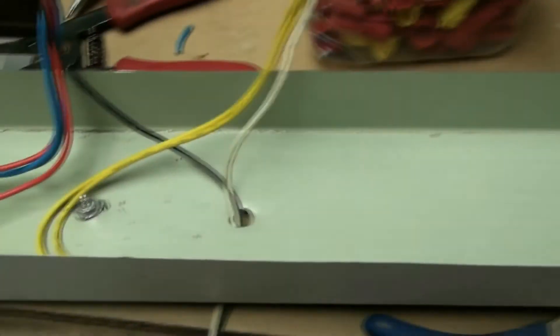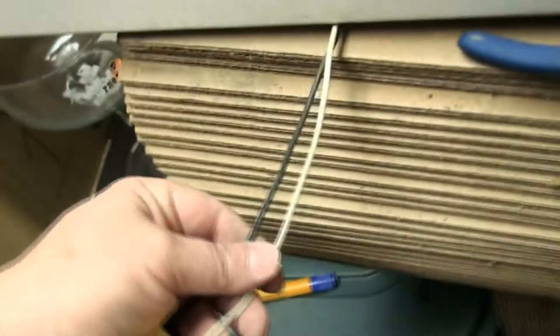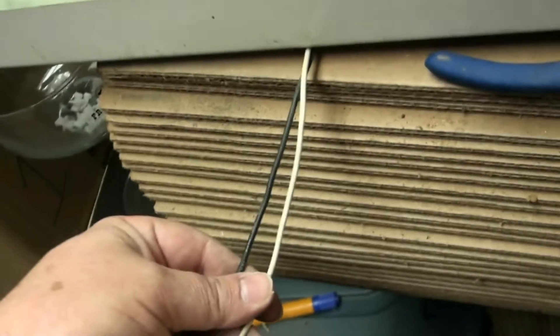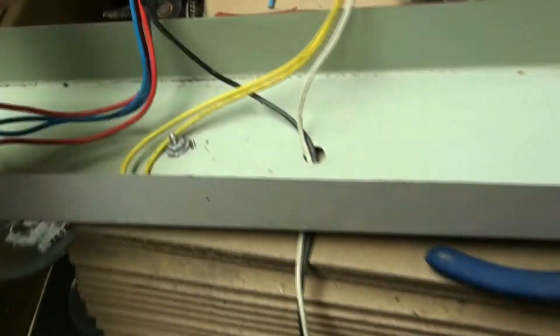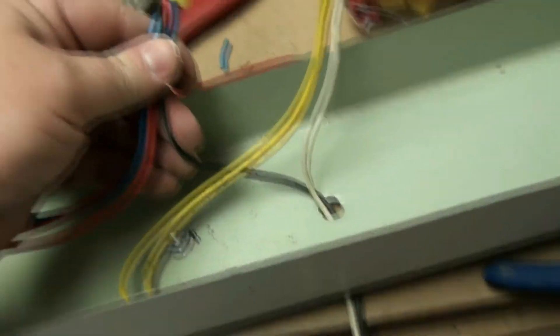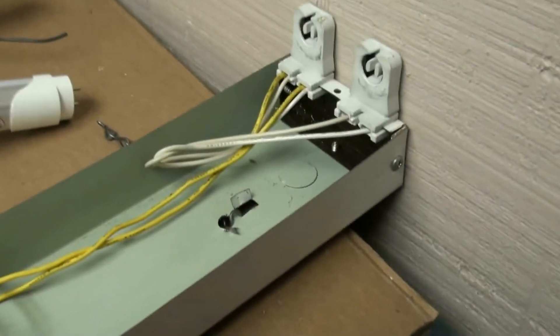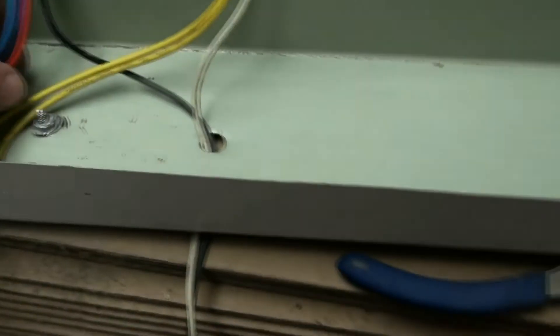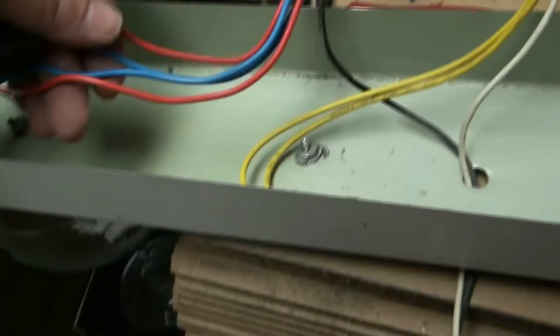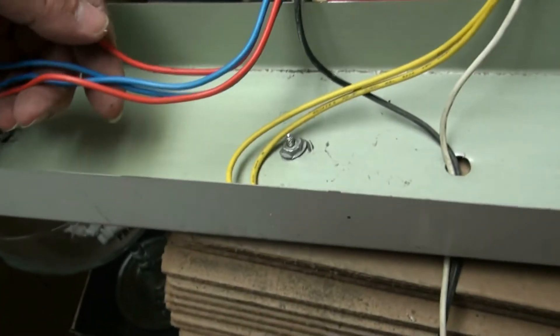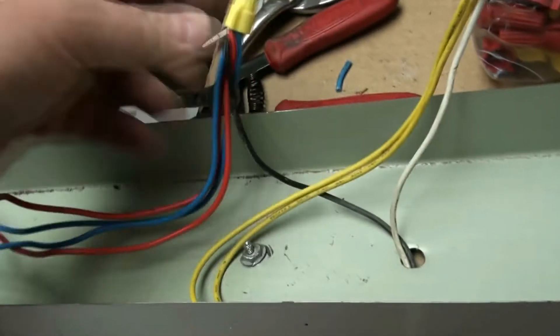All right, as you can see I removed the ballast. I've cut the wires and here is my source wire. I have the hot side going to the left and the neutral side going to the right. That's all you need to do, to make sure that you splice all four wires plus the feed to one.